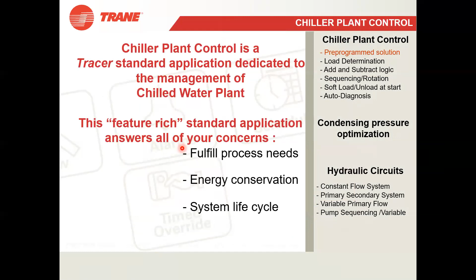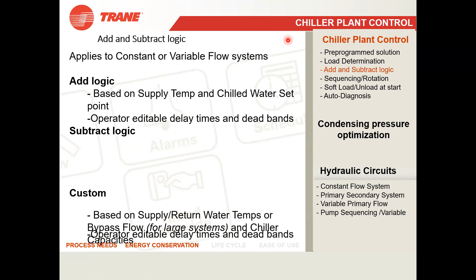This is the slide: add and subtract logic. So what is add logic, in a very simple way? Add logic means adding more chillers; you are switching on more chillers. Subtract logic, in very simple language: in the evening or afternoon, when less load is there, you are switching off one chiller after another. That means subtracting the chiller. Custom means everybody can understand. If the customer wants customization, suppose I want this particular chiller to run 220 hours in a year, or I want this particular chiller to run 150 hours, those kinds of customization can be done. So how does this add logic work? I will go to the next slide; that will be easier to understand.